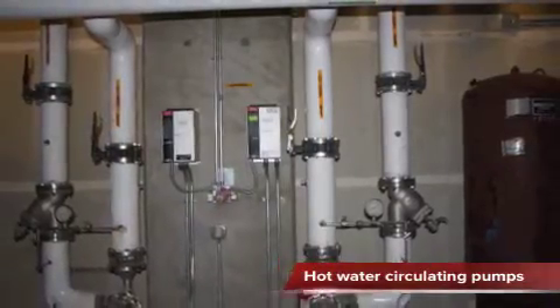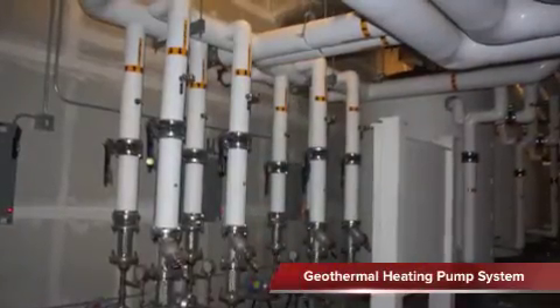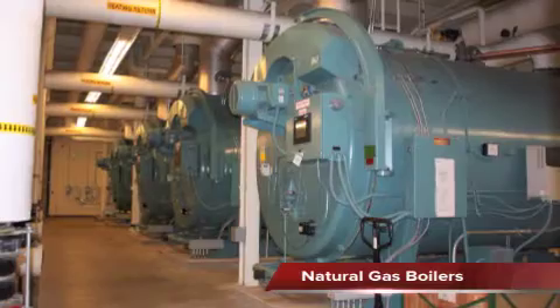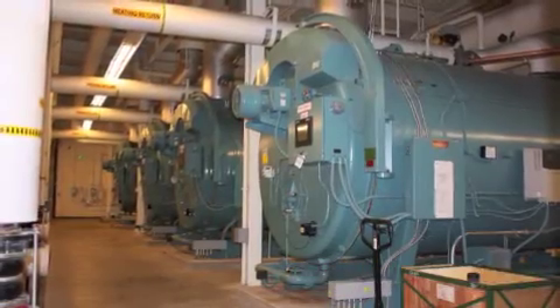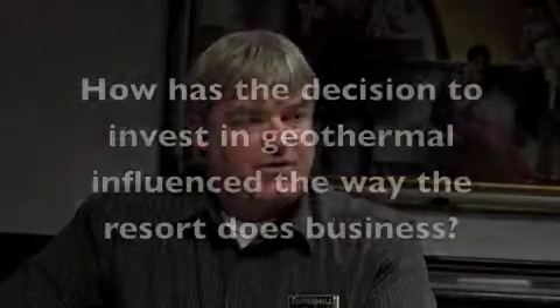We run what's called a hydronic system in our facility, meaning we heat water that goes to the facility, through the ventilation systems, and comes back, and we cool the building with chilled water. On the heating side, my boilers used to do all of that work, heating the water, sending it to the facility, then back to the boiler. We don't use our boilers anymore; geothermal does all of that for us.